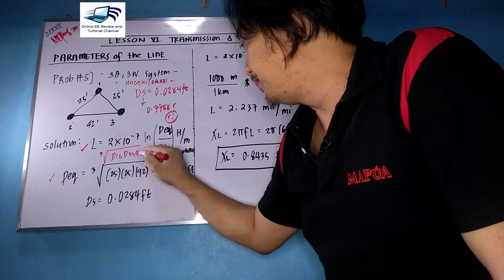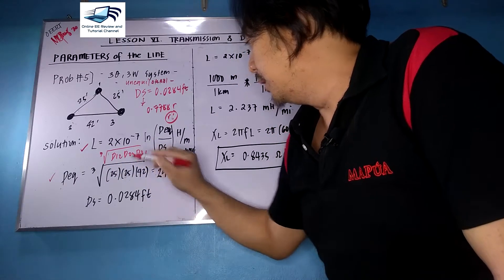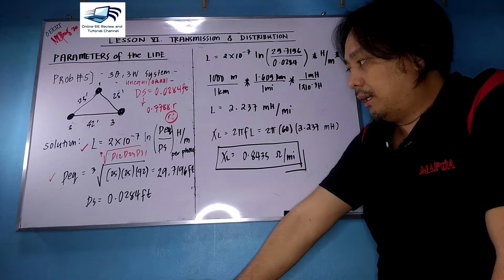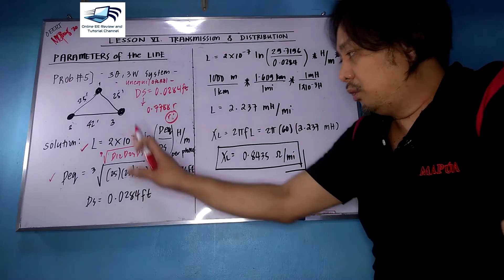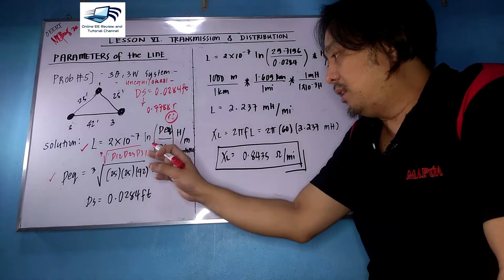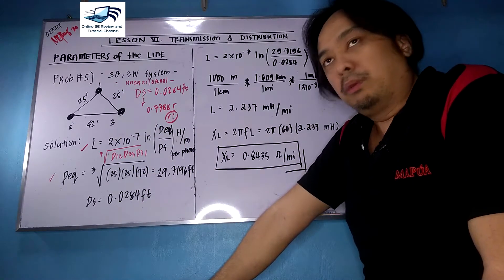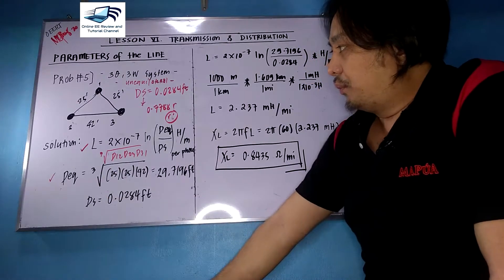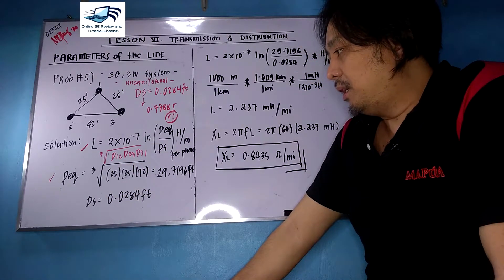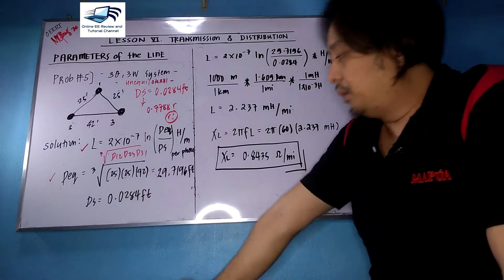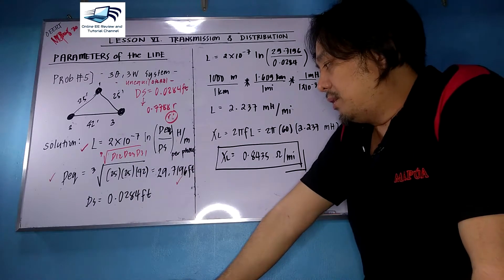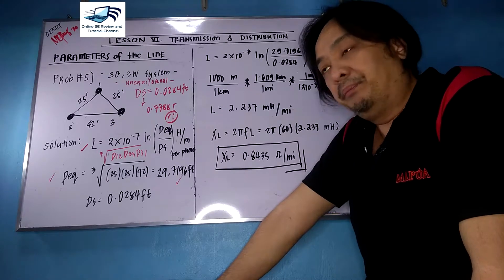We need to get D_eq first. From our last lecture, D_eq equals the cube root of D12 times D23 times D31. So we have the cube root of 25 times 25 times 42, raised to one-third. The answer is 29.7196 feet.